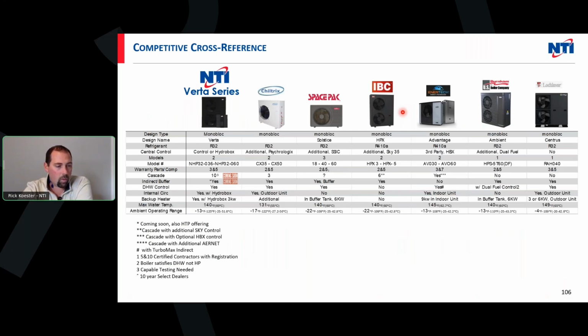We're all using primarily R32. These guys have all updated their equipment to R32. So as far as water temps go, we're pretty much a level playing field. We may say we can do a little bit more, for a short period of time. A lot of these guys are putting out the same piece of equipment, just branded under different names. So a lot of them are on that same level playing field. But to do a lot of what we do already in our control box, most have to go with additional controls. As you can see here, everything is included in the control box with our system.